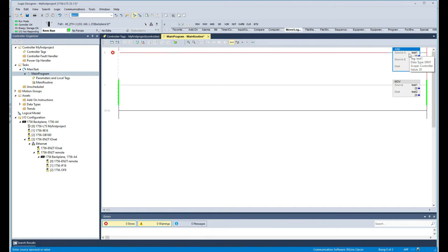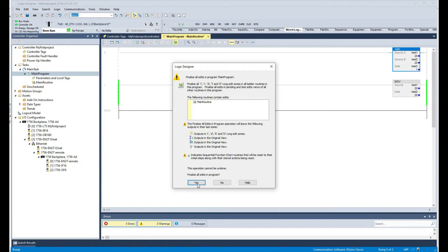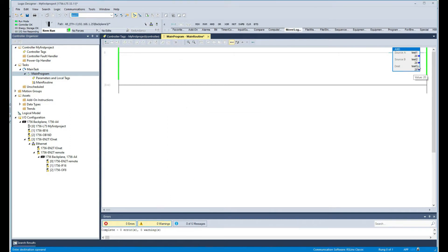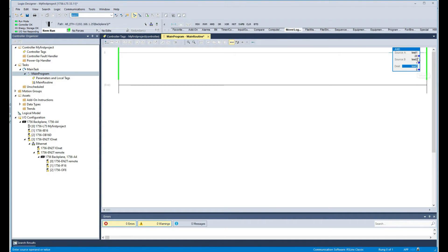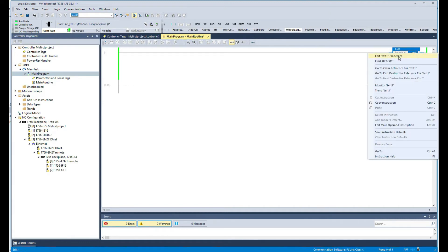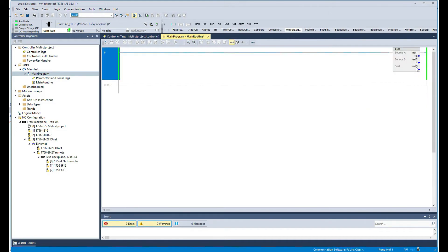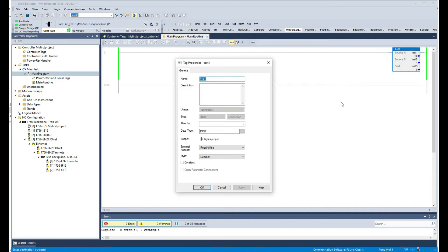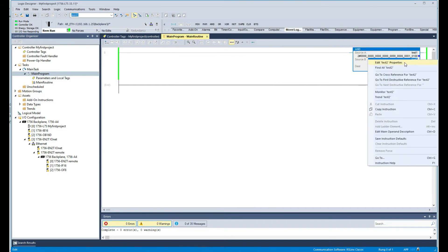The AND instruction essentially takes two values and performs a logical AND. I'll put here 'test three' as the destination. What it does is AND this value plus this value and shows us the result. Now, a better way of showing this is to display these values in their binary representation rather than decimal. We can right-click on the tag, go to Style, and change that to binary — this gives us a better understanding of what's going on.